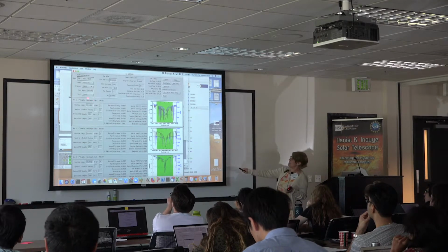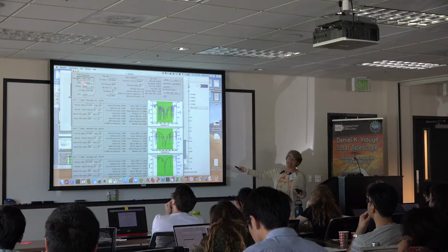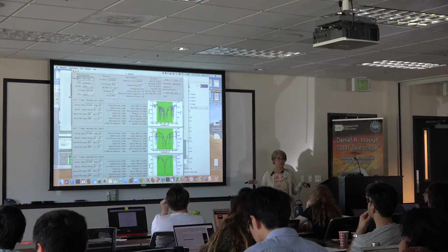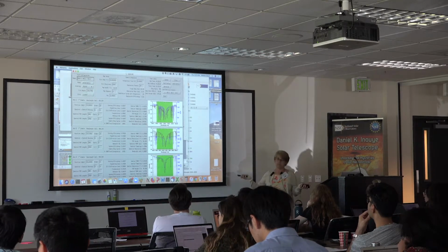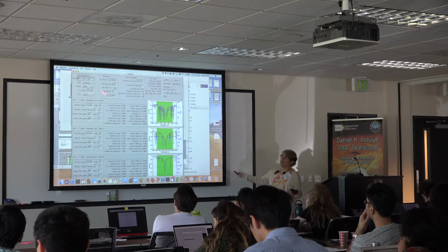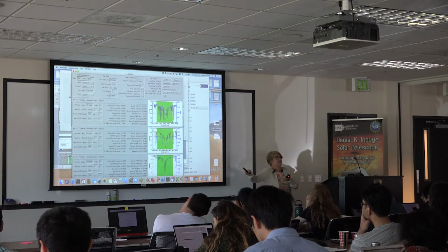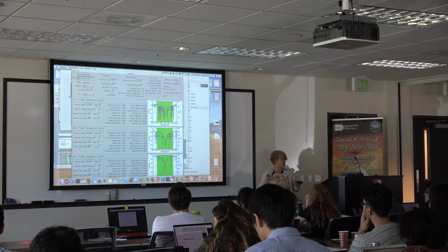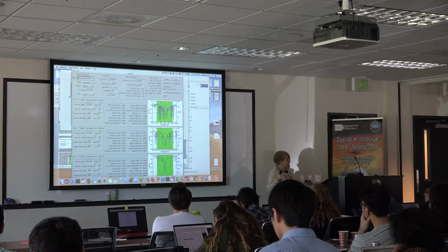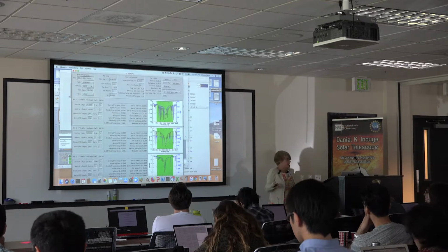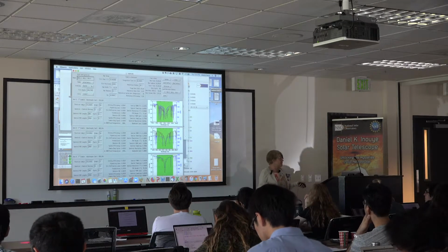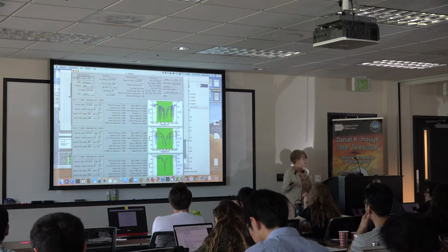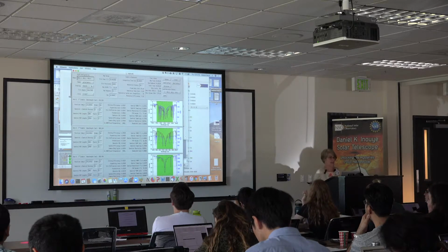Then you can select your slit. And again, this needs to be optimized to your science case. For example, if you're looking at things only in the far red, having the smallest slit doesn't make much sense, because the diffraction limit is anyway bigger than that. And so you're just starving yourself of photons that you could be using in a different way.